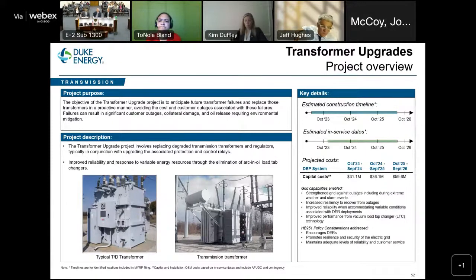Transformer upgrades, again, some parallels to breakers. I mentioned earlier, our transformers transform voltage from transmission levels to other transmission levels. So 500 kV to 230, 230 to 115. That's for connecting out to the various levels of the transmission system for bulk power flow. And then they also transform voltage from the 230 kV system, the 115 kV system, down to the 24 kV system commonly in the DEP area. So these are critical assets for serving our customers.